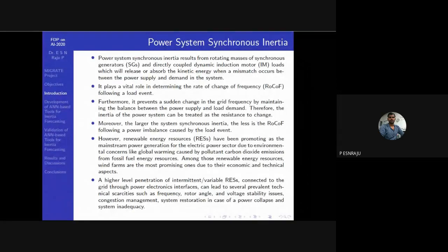Furthermore, it also prevents sudden changes in grid frequency. When there is a sudden drop in load or sudden change in generation, this inertia acts as a resistance to that change, so you can minimize frequency deviations or minimize the change in rate of change of frequency. When we have larger synchronous inertia, we will have lesser variations in RoCoF, or less difference between power generation and load demand.